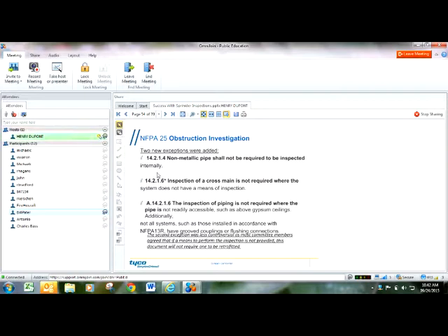The new edition of NFPA 25 has come out to say that non-metallic systems, in other words, plastic sprinkler systems, CPVC, an approved type of material for wet pipe sprinkler systems, are not required to have 5-year obstruction investigations. And if I was the authority having jurisdiction, I would probably still continue to ask them to do 5-year obstruction investigations. You're not going to get biologically influenced corrosion, or the system is not going to corrode because it's a plastic system.